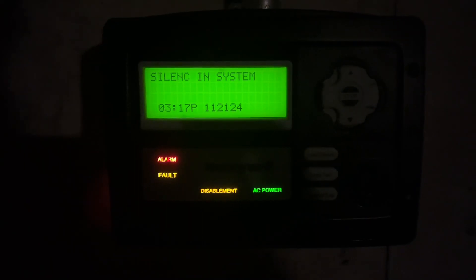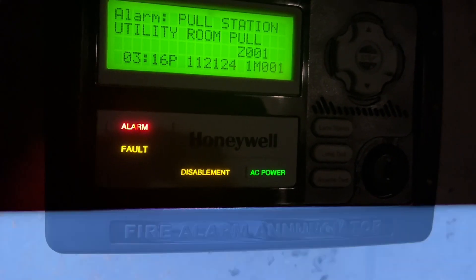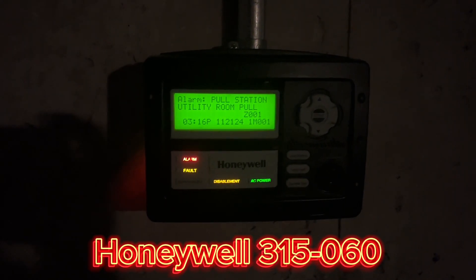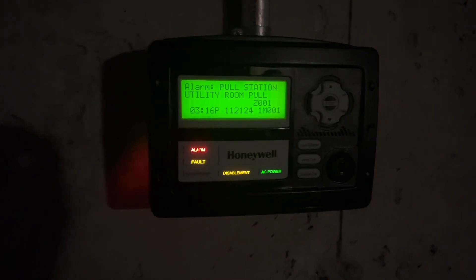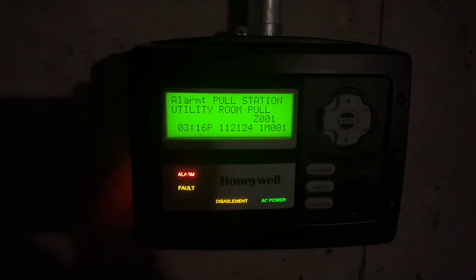So, first big surprise. I now have an annunciator on the system, but you can see it's not a typical ANN-80 — it says Honeywell, it says disablement, and it also has different functions. This is a Honeywell 315-060. It's intended for Australian systems, but it does work on the Fire-Lite panel because it uses the ANN-BUS.